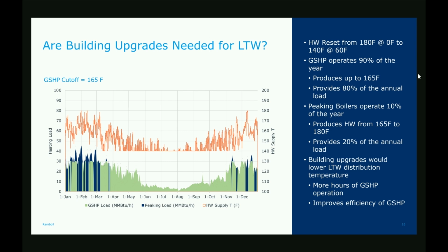For this baseload peaking, you could use it on a reset schedule so that if you need 180 or 200-degree water, you can produce that with your fossil-based boilers, which could be existing assets. In warmer temperatures, when hot water doesn't need to be as high, you utilize your heat pumps. With a 165-degree cutoff, heat pumps operate 90% of the year and cover over 80% of the load, with peaking boilers covering the rest. This helps get them set up, and in the future, as technology improves, we can cut out more fossil-based technology and implement more electric technology.